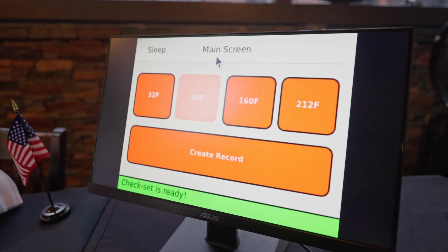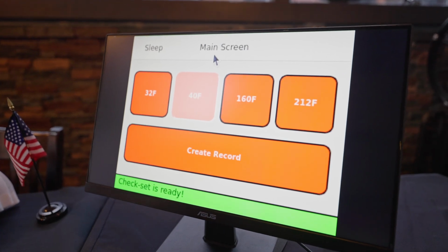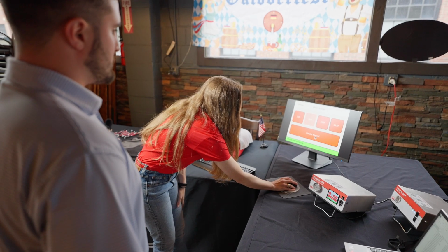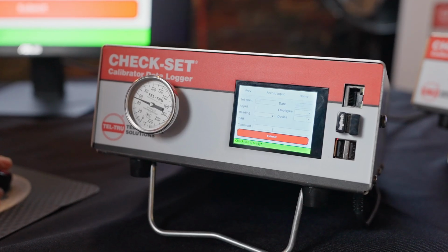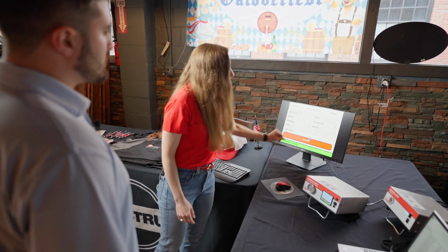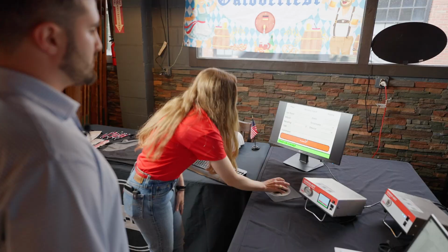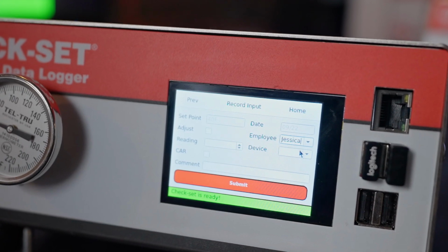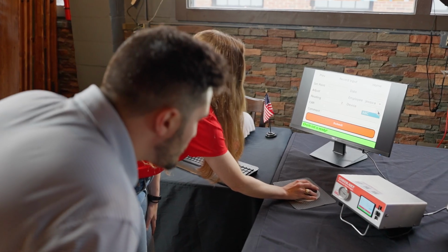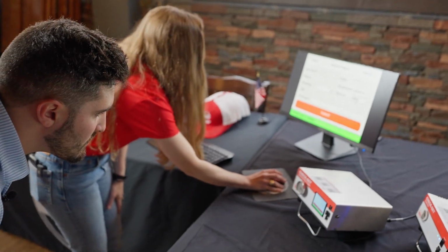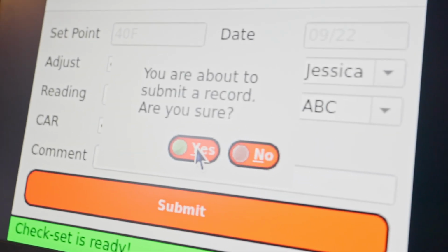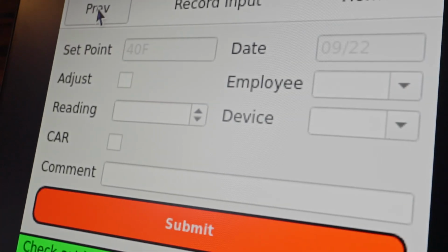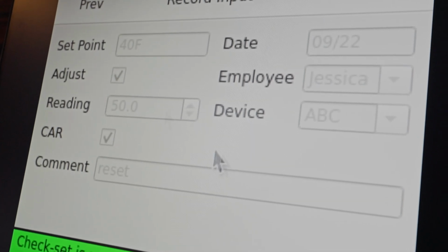I set it here to 40 degrees to take a reading. And if I want to go and create a record, now that the screen is green, I'd have the set point of 40 degrees. I have the date. I'll now select the employee here and I'll select the device. This is thermometer ABC. I'll save the record. And now I can go look at my previous records and you see there is the reading that I just took.